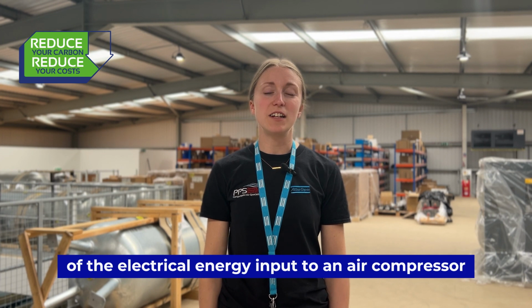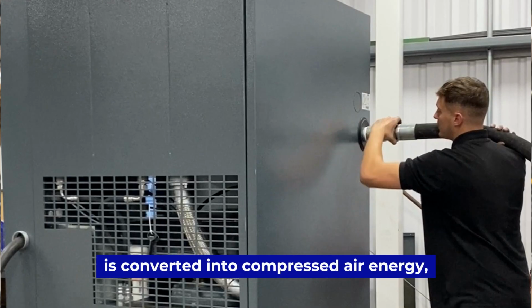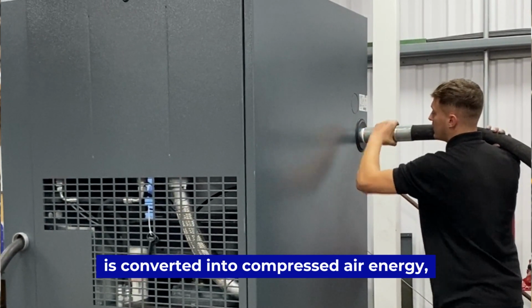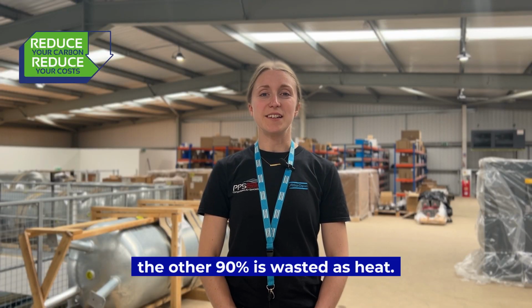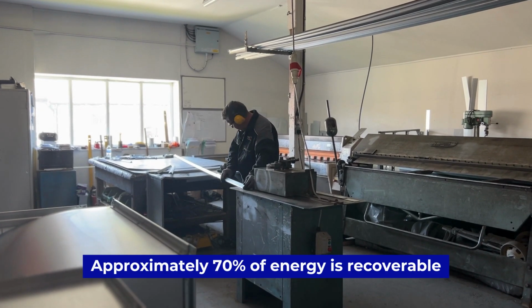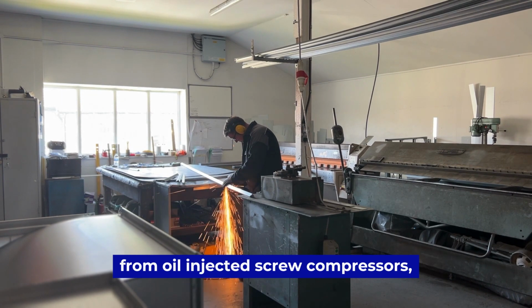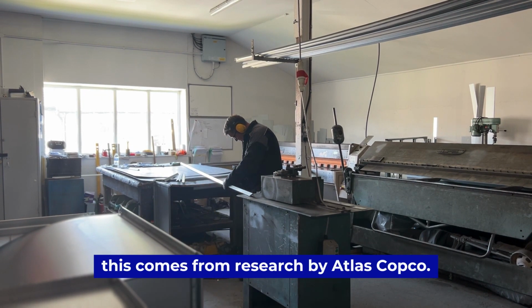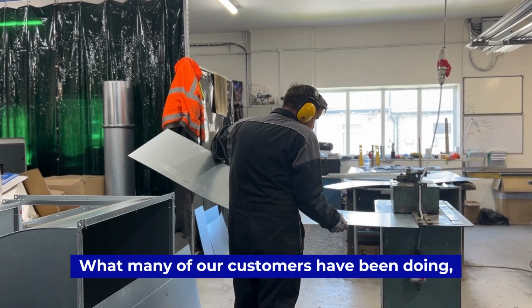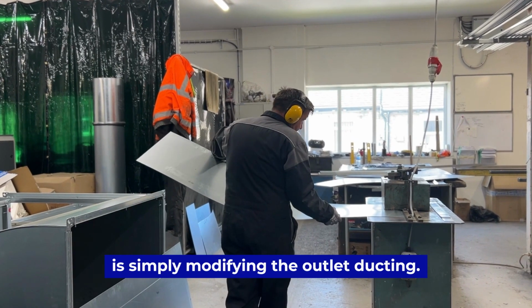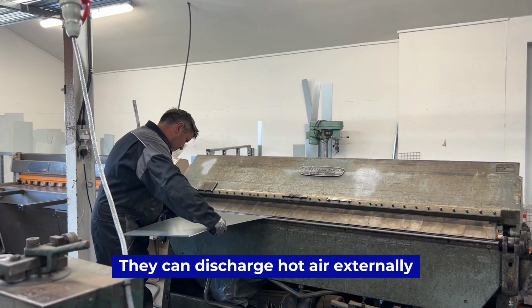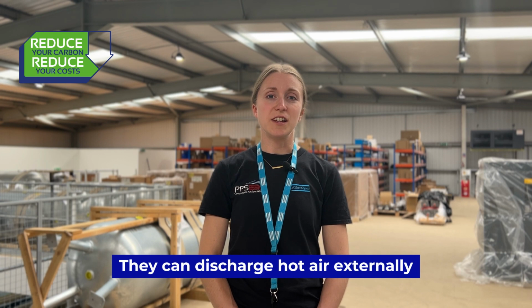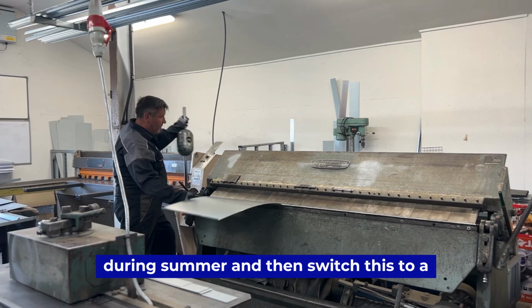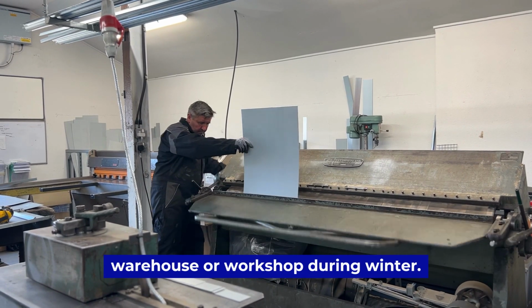Information from BCAS shows that only 10% of the electrical energy input to an air compressor is converted into compressed air energy. The other 90% is wasted as heat. Approximately 70% of energy is recoverable from oil-injected screw compressors. This comes from research by Atlas Copco. What many of our customers have been doing is simply modifying the outlet ducting. They can discharge hot air externally during summer and then switch this to a warehouse or workshop during winter.